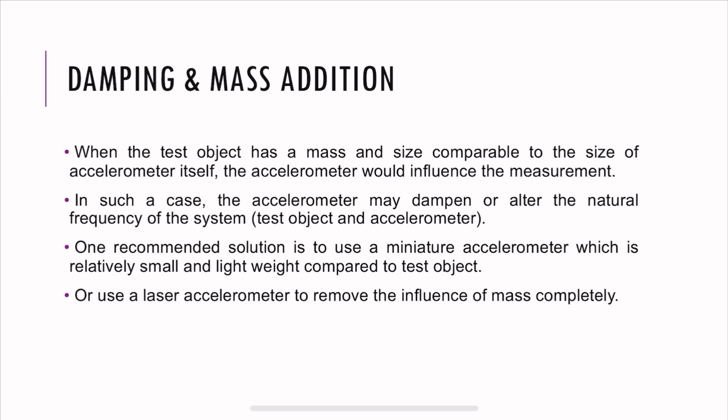One recommended solution is to use a miniature accelerometer, which is pretty tiny and has very less mass. But if that is still influencing your measurements, the best bet is to use a laser accelerometer, also called a laser vibrometer. In that case, you're using laser or light to measure the vibrations on the surface. So you're removing the influence of mass completely.